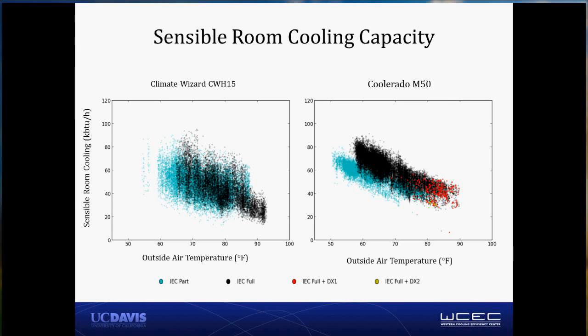And so we can look at the capacity for sensible room cooling. And this is the way that you might look at the system if you were thinking of replacing a recirculation-only system. And so it's important to remember that the capacity, and you'll see the coefficient of performance if you look only at the room cooling, actually decreases as the outside air temperature increases. The system's total capacity is increasing significantly as outside air temperature increases, so it's doing a great job of cooling ventilation air, but the capacity that's impacting the thermostat in the space is decreasing as outside air temperature increases.